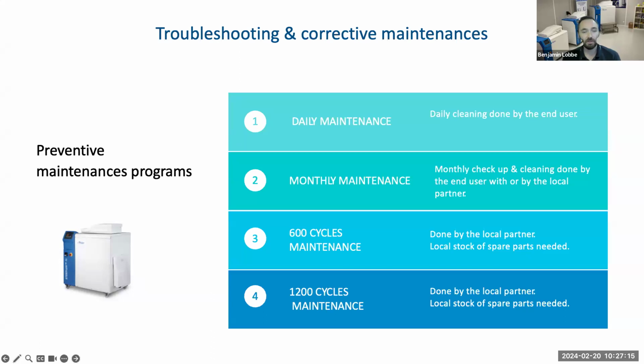In terms of maintenance, there are 2 major maintenances to do. I wrote 4 here because the daily maintenance is more like part of a daily cleaning after the end of use, after using the unit. The end user is invited to take care of the unit, and when possible, between cycles, to clean the basket when we remove the waste, or to clean the top of the machine, to ensure that the unit will last a long time, and that we don't need to perform maintenance often because we have some remains of waste, for example, locked at the loading door. So this is just a basic maintenance done by the end user, just the cleaning of the unit, for number 1 and number 2.